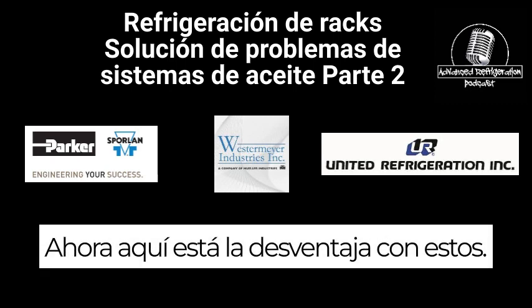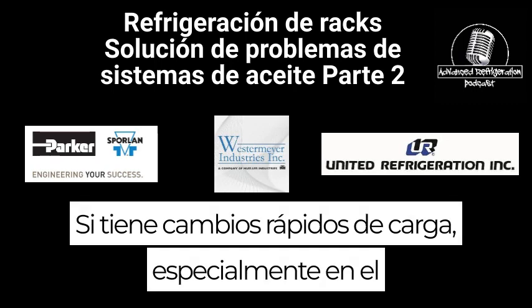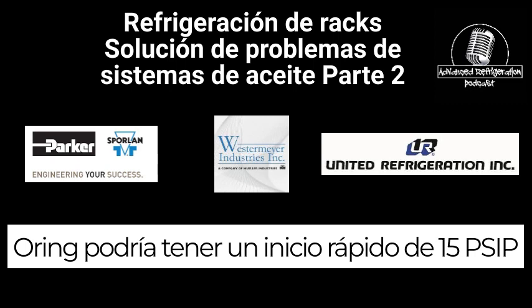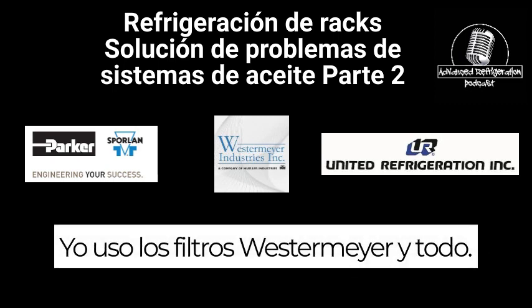Now, here's the downside with these. If you have rapid load changes, especially on the Temprite separators with the rubber O-ring, rapid load changes or on startup, you could blow that O-ring. You could have a 15 PSID rapid startup pressure drop across that filter and blow that O-ring. I see it a lot, prematurely blow. So I do not like to use Temprite filters in anything. I use the Westermeyer filters in everything.